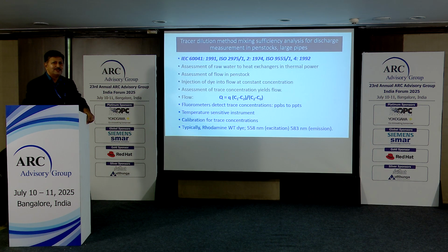Again, for large diameter pipes, one of the test methods we use is the dye tracer method. This has been used by us at many sites, including the largest in the country, the 255 megawatt turbine at the Tehri project. In this method, the principle is that we need to introduce a dye. It can be a radioactive or non-radioactive dye. Mostly we use rhodamine WT, a chemical that luminesces when excited by a wavelength of around 558 nanometers, and you get an emission spectrum. You can use the photon counting method to determine the concentration of the dye in the water.